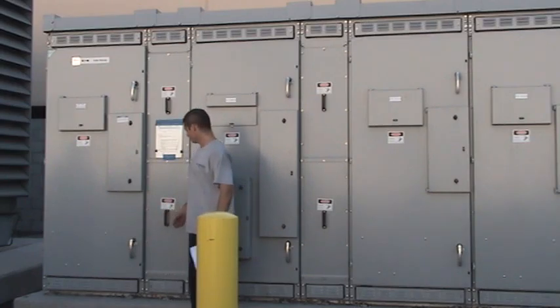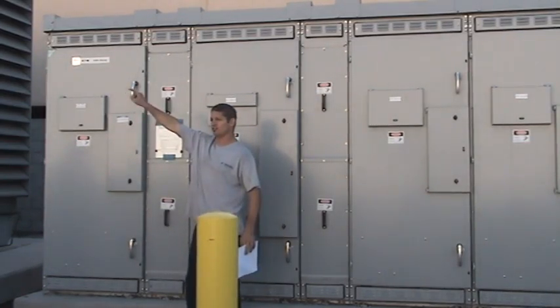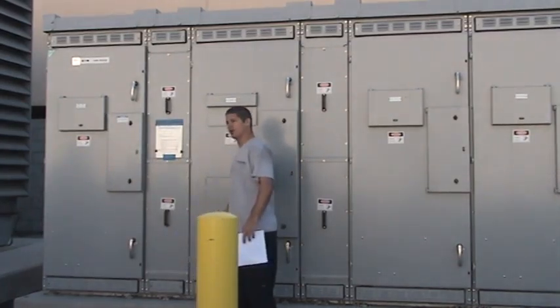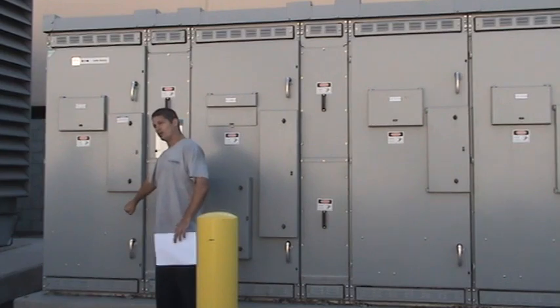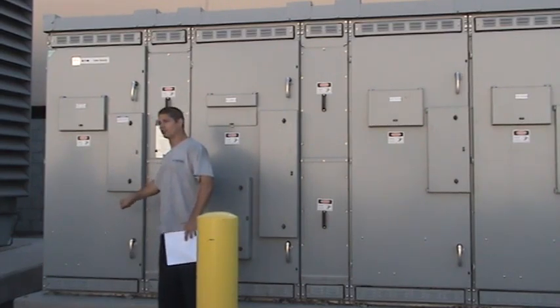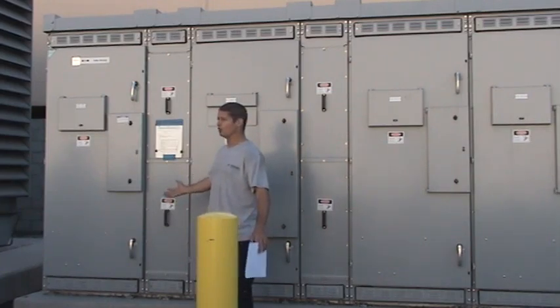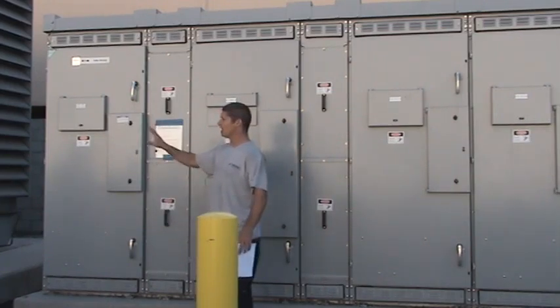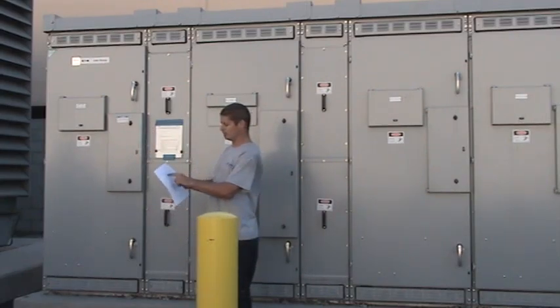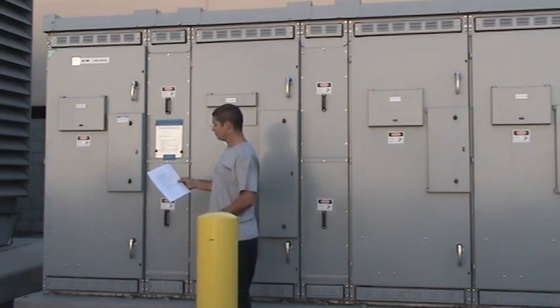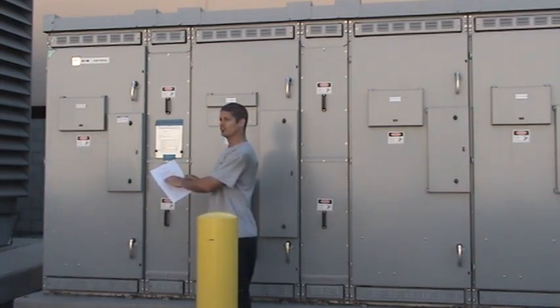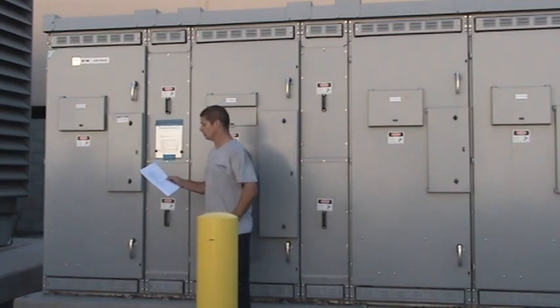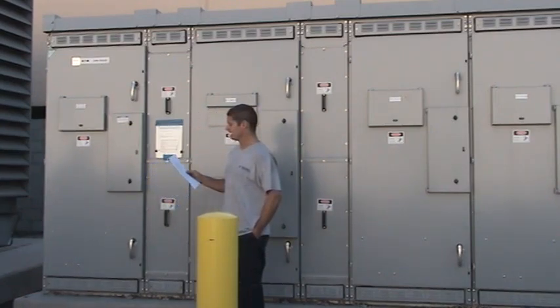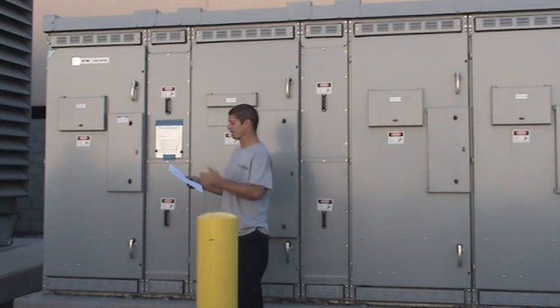Basically, there's a switch on the other gear, on MV13 over there, in the first compartment, that has a hand, auto and manual switch. And the normal state for this gear is in the auto position, right? So in auto, the outline over here shows you the position of all the switches. When it starts in that position, both mains are closed. You've got MSV13 main closed, and MSV13 tie is open over there, right? So the tie is open on that side.